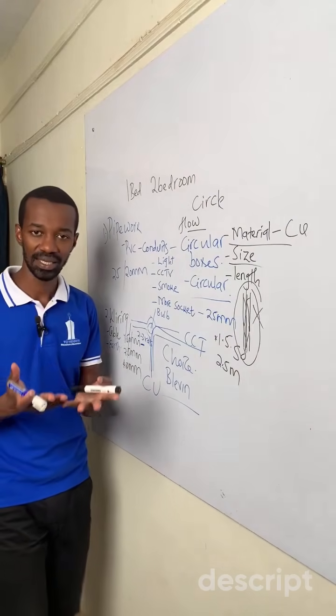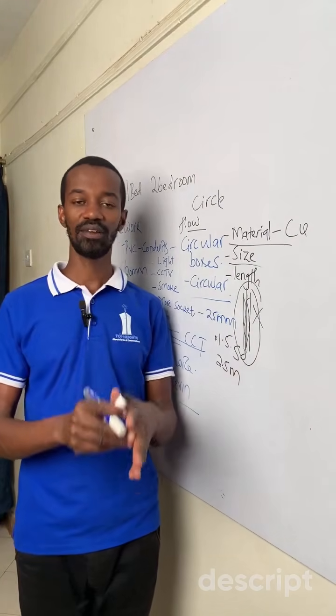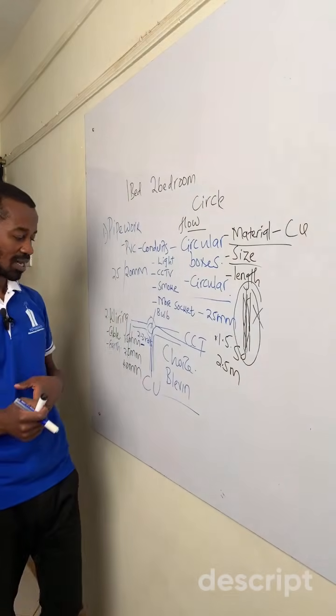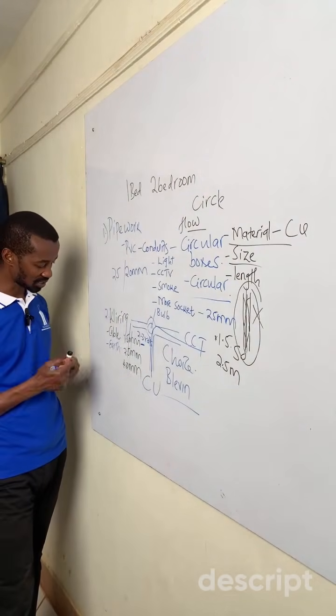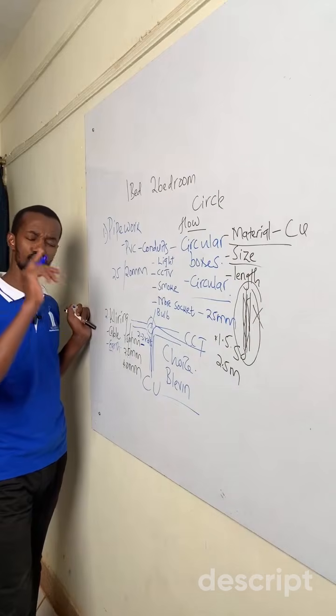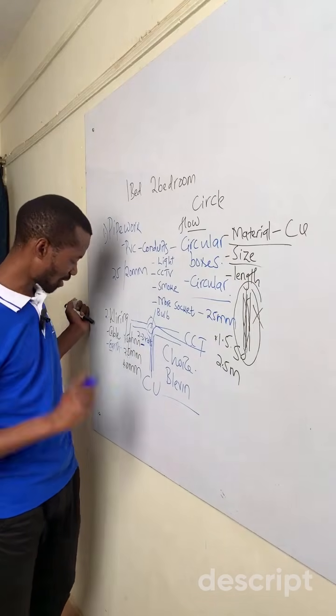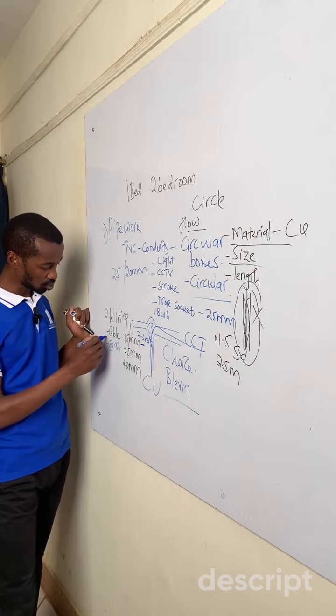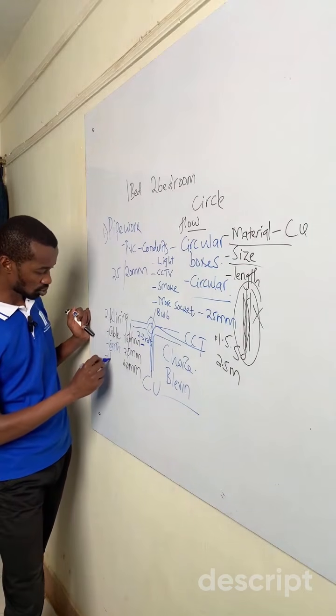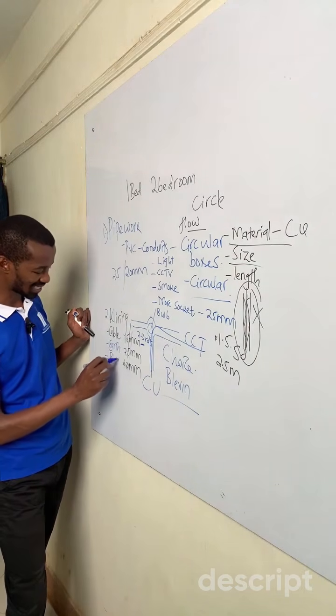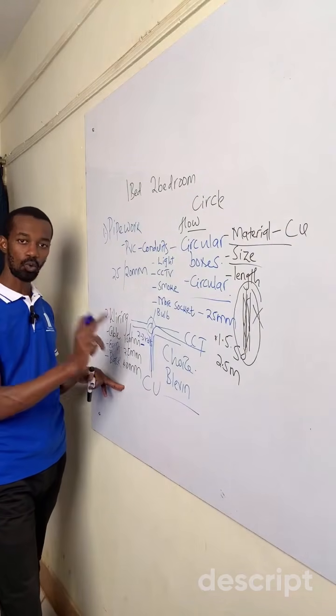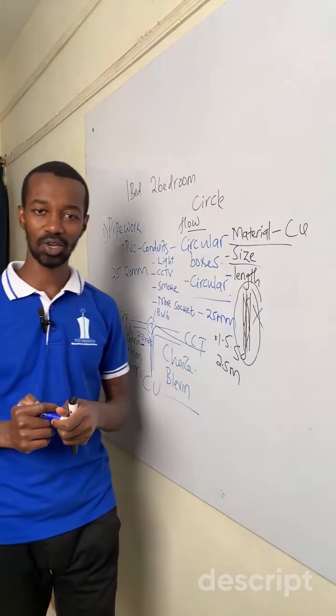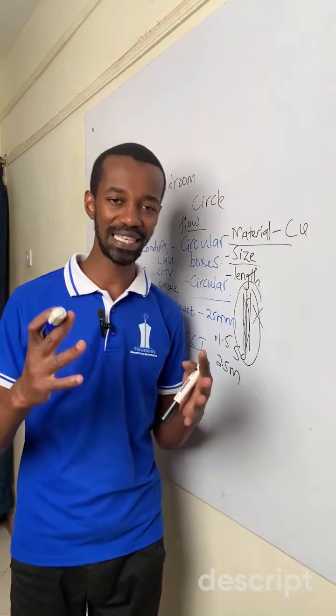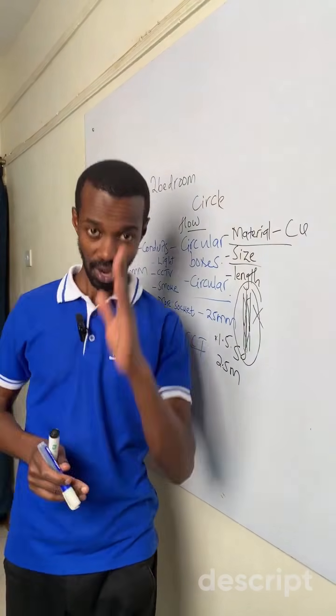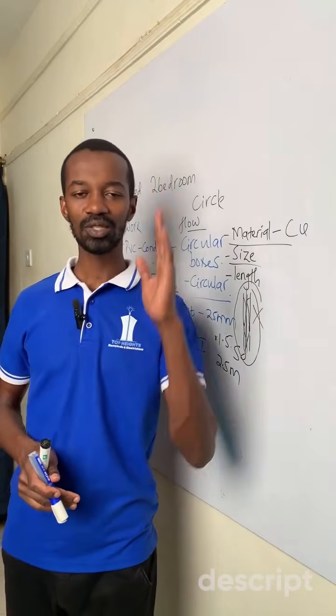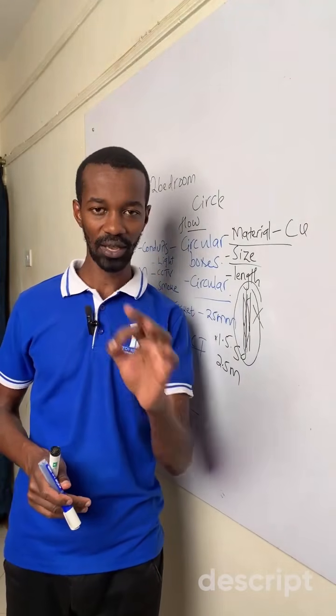So you find that in many cases, when we have a switch, we don't have the provision for the earth connection. So we will require a single roll for earthing. Do not, my top bosses, omit earthing. So we require a single roll. We will also require another single roll for black cable, and that is it when it comes to light wiring. When it comes to sockets or power outlets, my top bosses, we definitely require 2.5 for the red cable, for the black cable, as well as for the earthing cable. 2.5, no compromise.